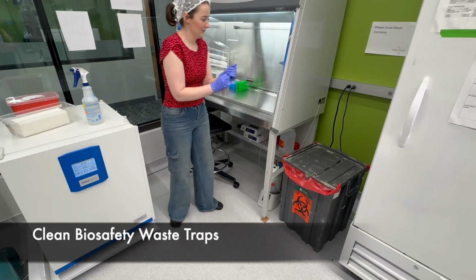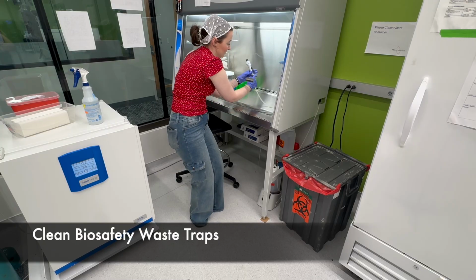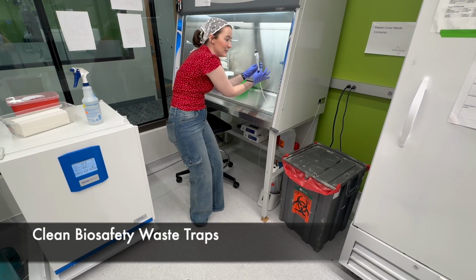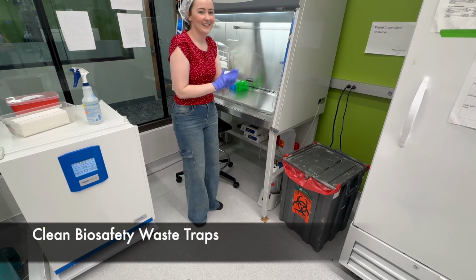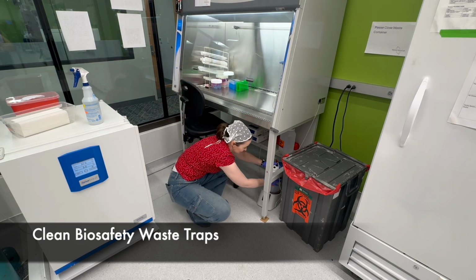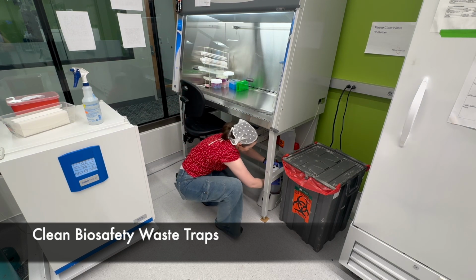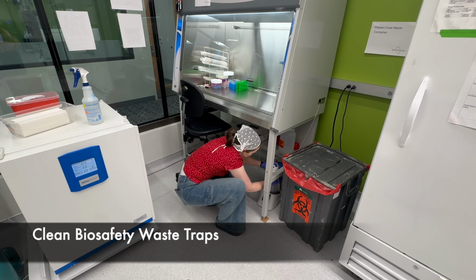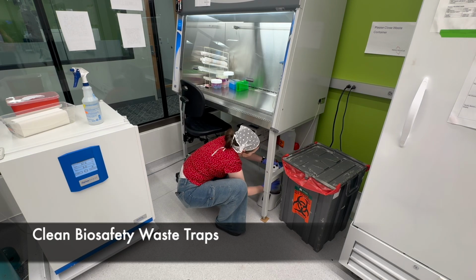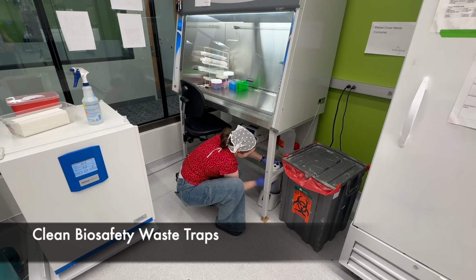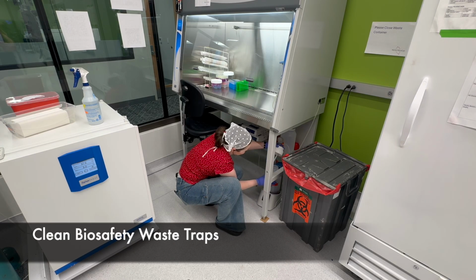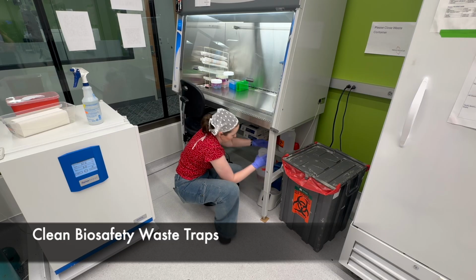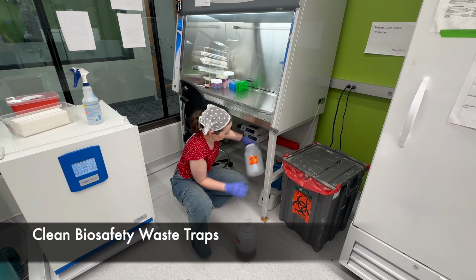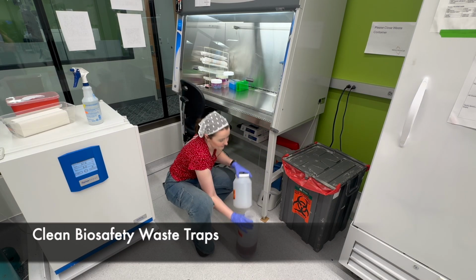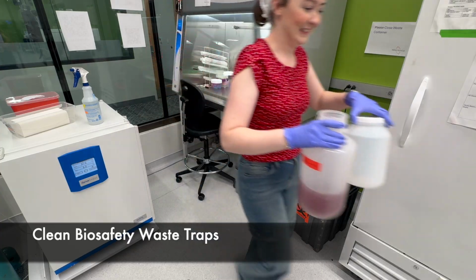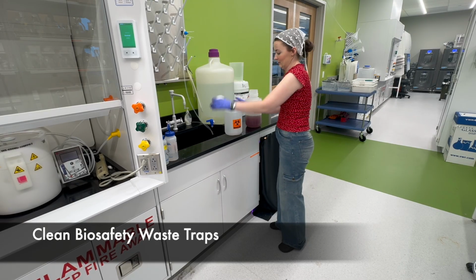The next task is to clean the biosafety waste traps. First, she is going to release the vacuum pressure from the biosafety waste trap by clicking on the aspirator. Next, she's going to go down and unscrew the top of the biosafety waste trap from the base of it. If this is absolutely impossible, you may not have released the vacuum appropriately. So make sure that you release that vacuum with the aspirator before. Next, she's going to grab the container that we're going to pour our waste in because you don't want to put bleach in that original one.